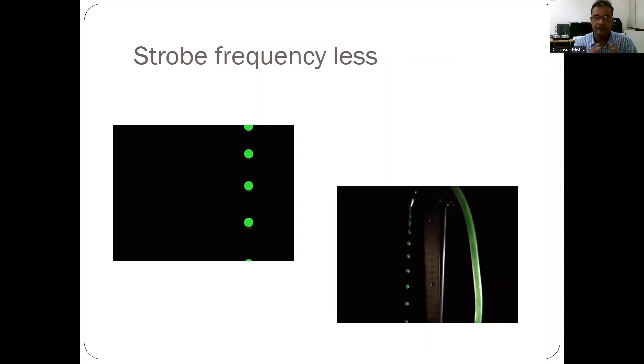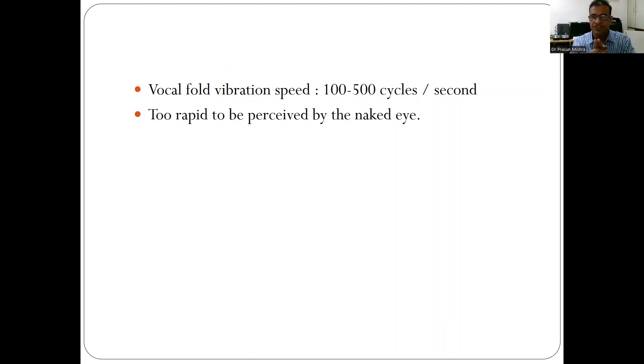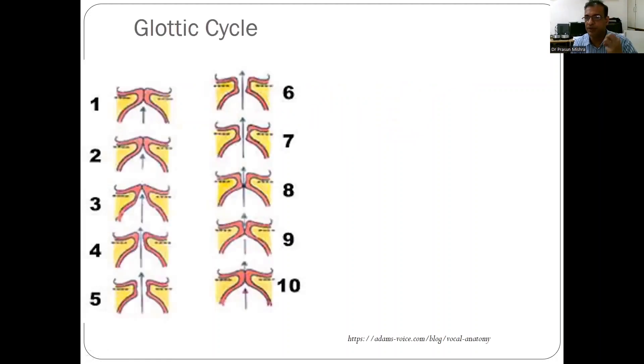Anything moving very fast cannot be perceived by the naked eye, as the retina perceives it as a single image. Vocal folds vibrate at a speed of 100 to 500 cycles per second — obviously the naked eye cannot perceive this. In normal video laryngoscopy, we only see the opening and closing of the vocal cords; the individual vibrations are not visible. To see these vibrations, we need a strobe light flickering between 100 and 500 Hz — that is why stroboscopy was developed.